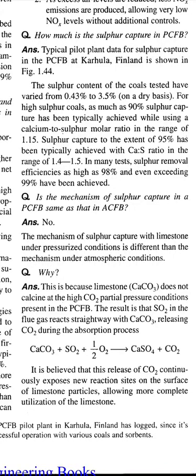Question: Is the mechanism of sulfur capture in a PCFB the same as that in ACFB? Answer: No. The mechanism of sulfur capture with limestone under pressurized conditions is different than the mechanism under atmospheric conditions. This is because limestone, CaCO₃, does not calcine at the high CO₂ partial pressure conditions present in the PCFB.